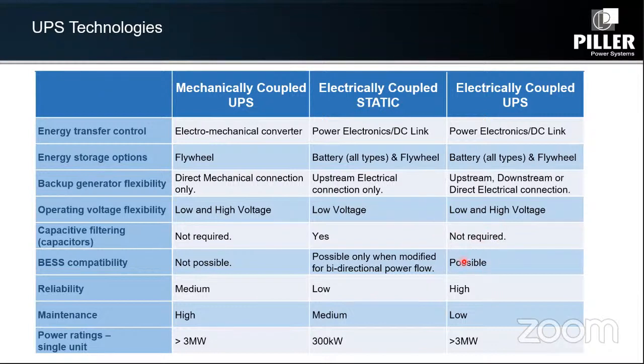We have BESS compatibility, and the reliability figures we can talk about. We don't have time now, but we can provide data in terms of MTBF, comparing it with any technology based on IEC or MIL standards. System module is where the difference is—we could have a single module of up to 3.2 megawatts, meaning you need fewer components when building larger facilities.